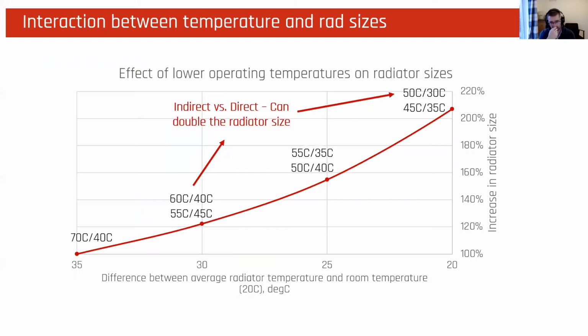Just to put this into context in terms of, well, how much bigger do these radiators become? If we look at this graph, which shows the increase in radiator size that results from moving from a 70-40 counterfactual of maybe 3 or 4 years ago up to supplying radiators with a 50-degree flow temperature, they're doubling in size. And even actually going from more recent radiators such as 60-40 down to 50 degrees, they're about 1.5 times the size, if not more. And so these start to become either very wide or very deep, which gives its own kind of design challenges. And obviously the cost goes up.